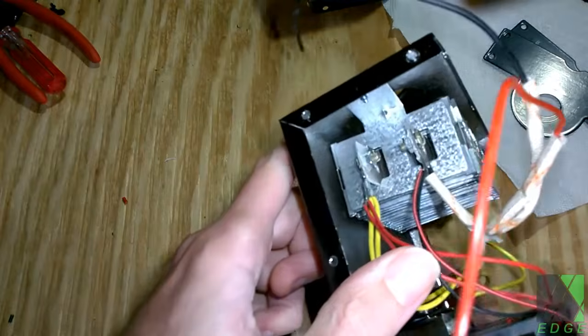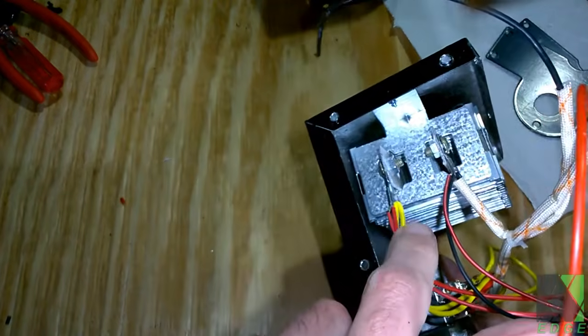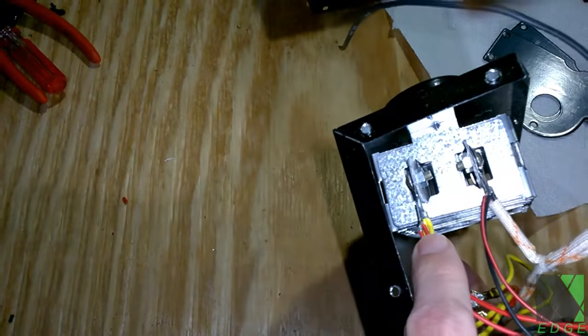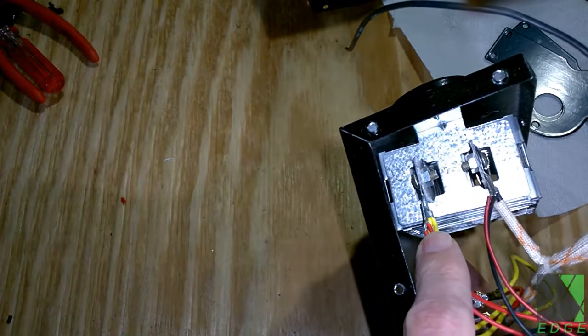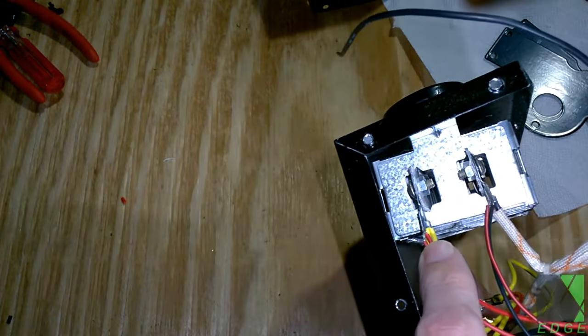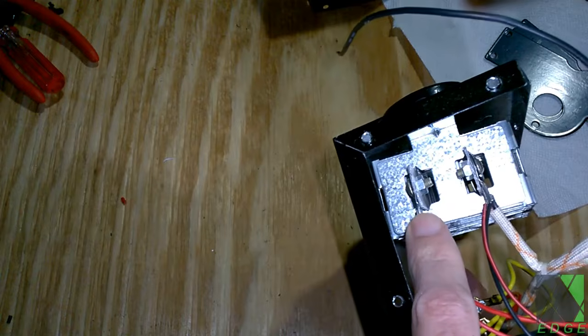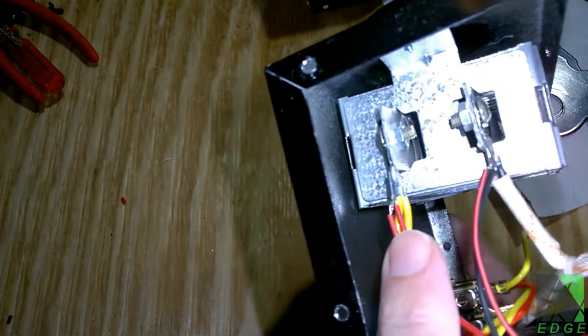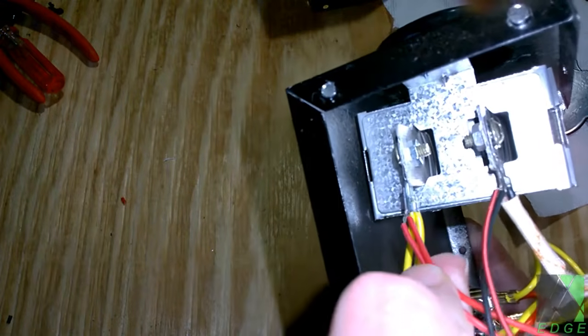If you look over here, there are two terminals, and one is positive. You can see the fans. Wow, that crimp looks really bad, the wires are just hanging off. So that's why I open these heaters, to check the wiring, and I would definitely need to redo this, put some heat shrink or do something. That's terrible, the fan wire is just hanging on there.